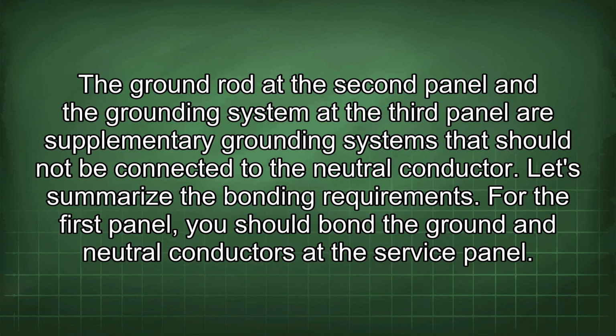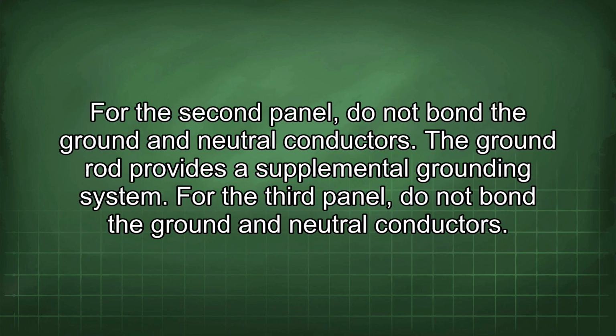The ground rod at the second panel and the grounding system at the third panel are supplementary grounding systems that should not be connected to the neutral conductor. Let's summarize the bonding requirements. For the first panel, you should bond the ground and neutral conductors at the service panel. For the second panel, do not bond the ground and neutral conductors.